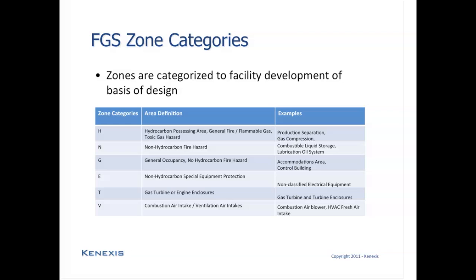The next type of zone is a G zone. This would be general occupancy, where there's no hydrocarbon fire hazard. And this would include things like accommodations areas of oil and gas platforms, control rooms of any typical process facility, workshops, other areas that are normally occupied by people, but where chemical processing does not occur.